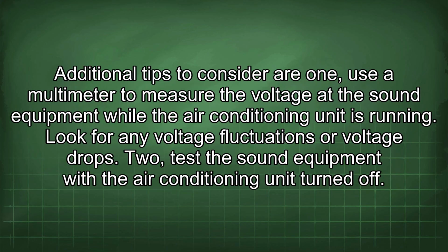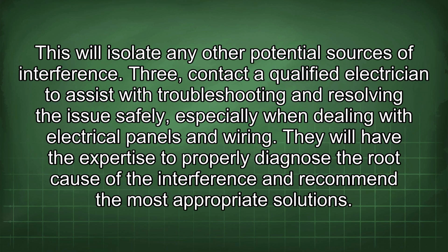Additional tips to consider are: 1. Use a multimeter to measure the voltage at the sound equipment while the air conditioning unit is running. Look for any voltage fluctuations or voltage drops. 2. Test the sound equipment with the air conditioning unit turned off. This will isolate any other potential sources of interference. 3. Contact a qualified electrician to assist with troubleshooting and resolving the issue safely, especially when dealing with electrical panels and wiring.